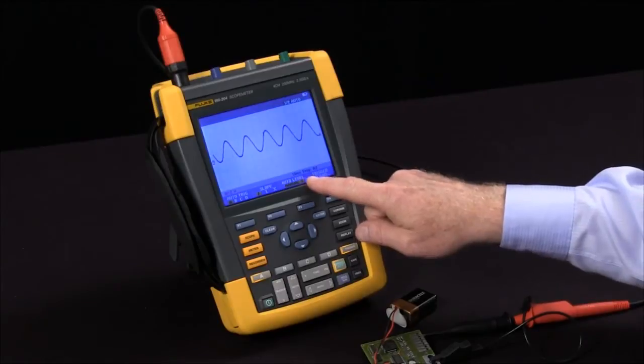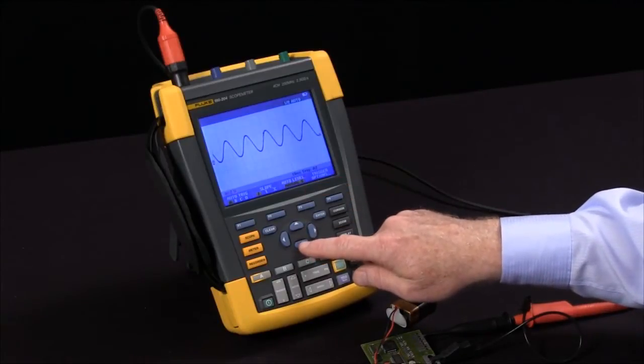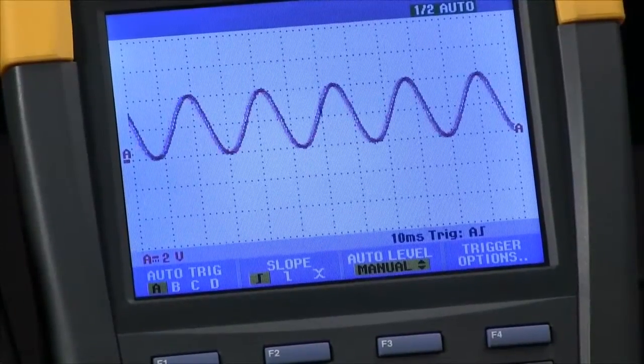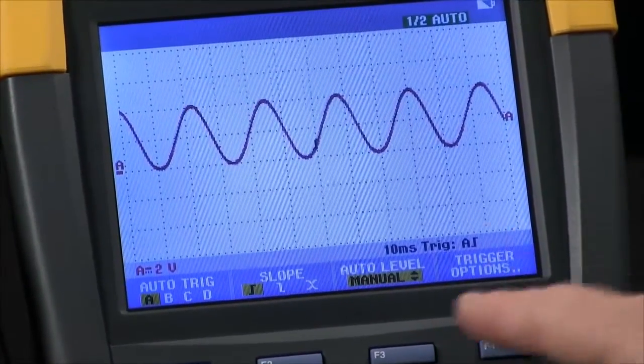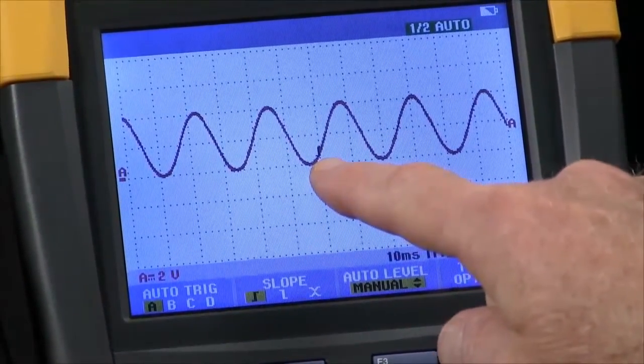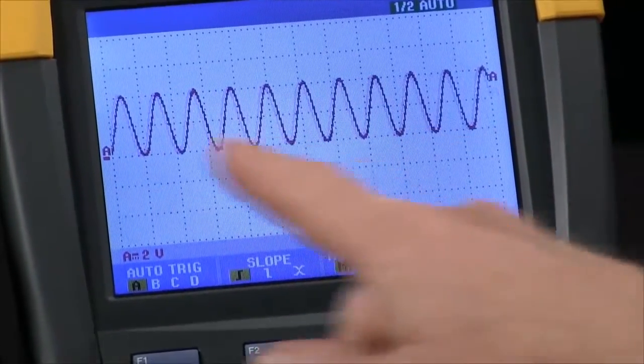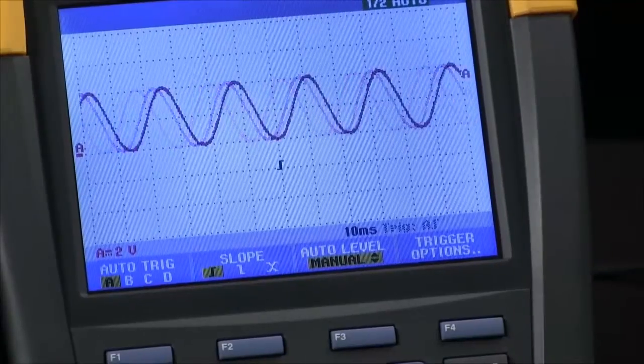If I use my arrow keys to reduce that level, you'll note that the waveform shifts a little bit left and right. I'm now triggering near the bottom of the waveform. If I come outside of the waveform, I'll lose sync and things will no longer be stable.